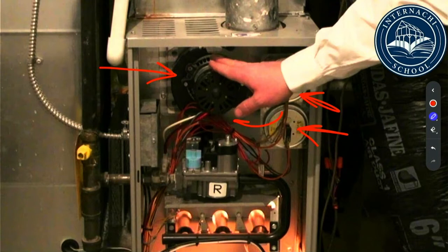Then we're going to have a silicon igniter down here. Our gas valve will open up, send gas in there, and then we're going to have a flame sensor somewhere in there to make sure that the gas actually ignited. Once that happens, it's going to send another signal back to the computer, and the computer is going to let it go to the next stage. Then behind this hand, like a secret weapon, there's going to be a high limit switch, or basically another thermostat, in there. And if this blower fan is not running, then this furnace is going to get hotter and hotter and hotter until finally it's going to overheat.